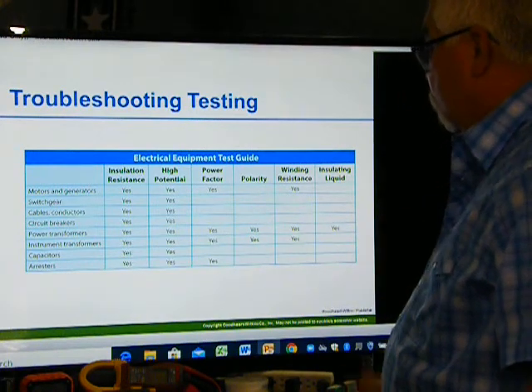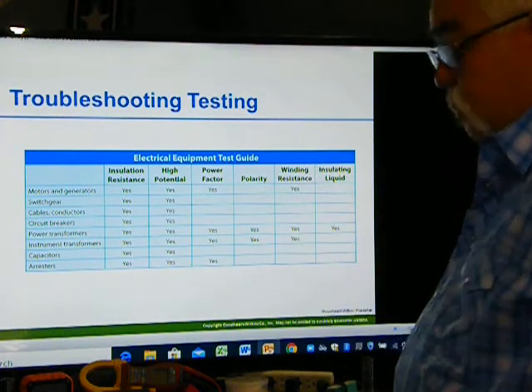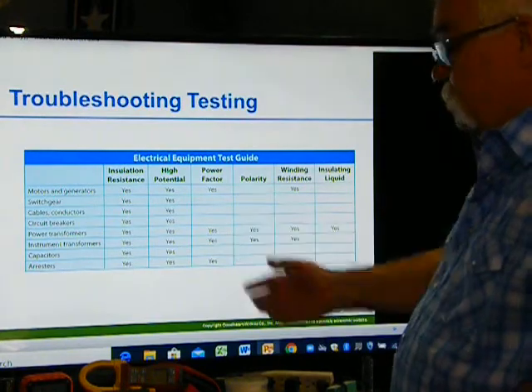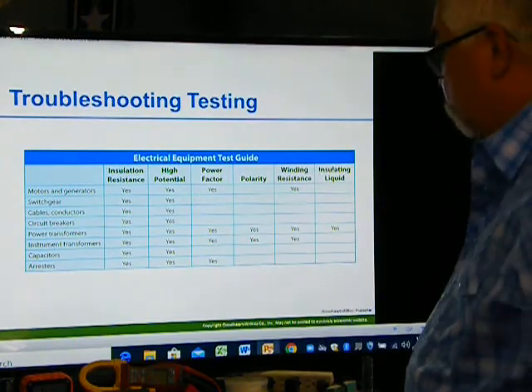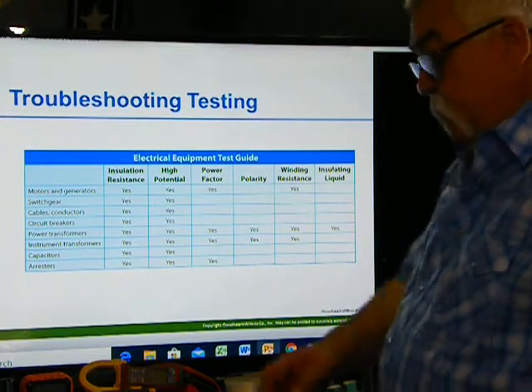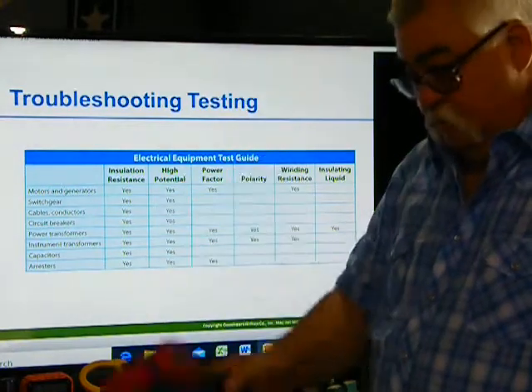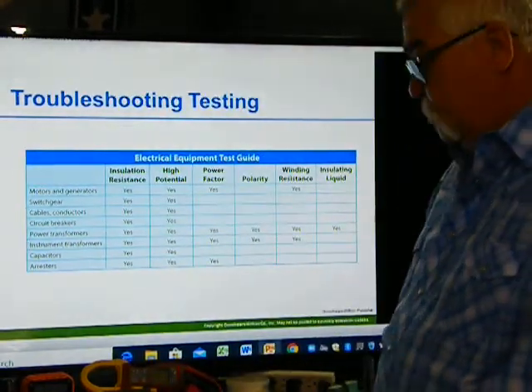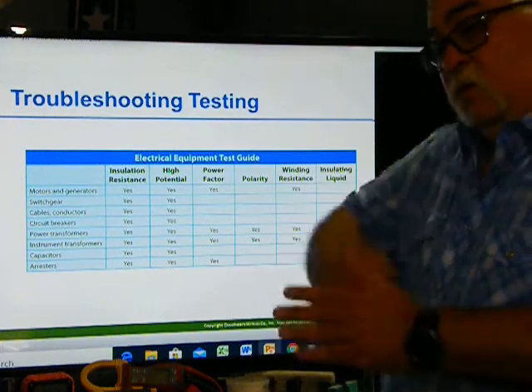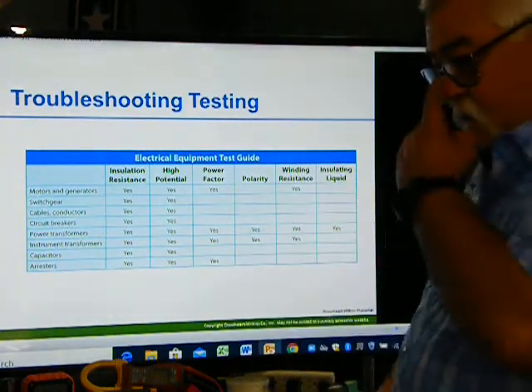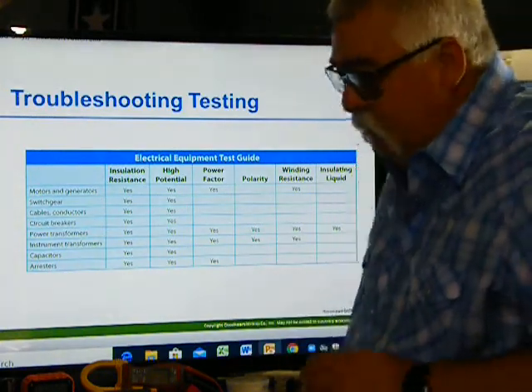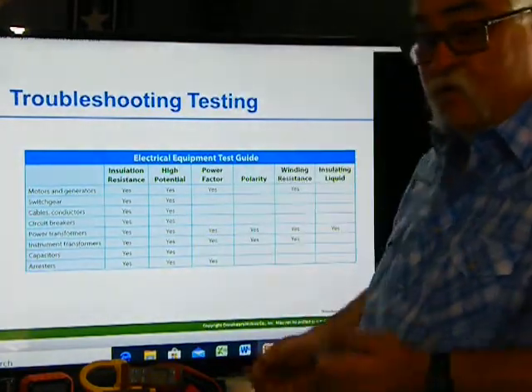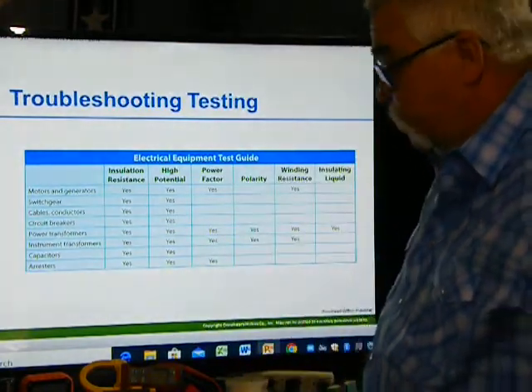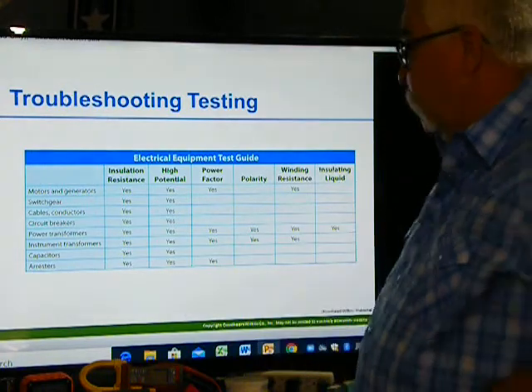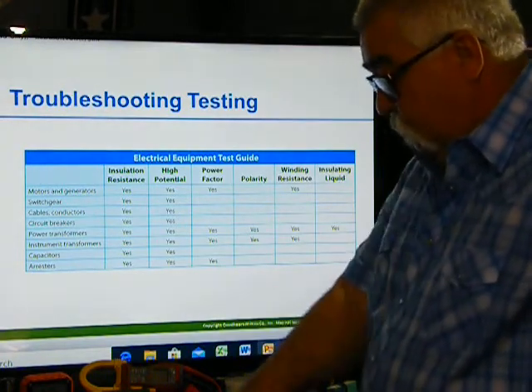So this is just a test guide on things that you need to test. Okay, what do you use? Well, it depends on what test you're doing. If you're checking temperature, you're good. If you're checking resistance of insulation, you get a megger. The ones I had back in the day were crank. I've never used one that was electronic. We had one, but I never got to use it. All I ever used was the crank one, and it sends out a voltage signal.